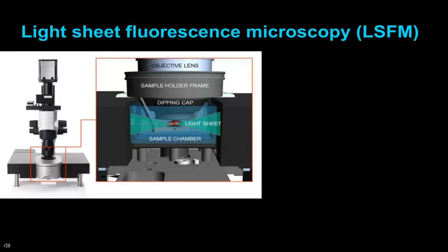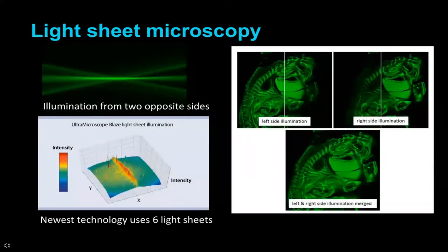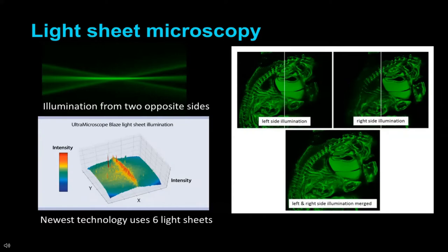Light sheet microscopy—the principle is very simple. The illumination comes not in the same direction as the lens, but perpendicular to the imaging lens. Often you will see illumination from both sides. The light sheet is stable but the sample moves up and down so you can capture the whole sample. The newest technology, such as the UltraMicroscope Blaze, uses six sheets of light—three from each side—and you gain more detail by using illumination from both sides.